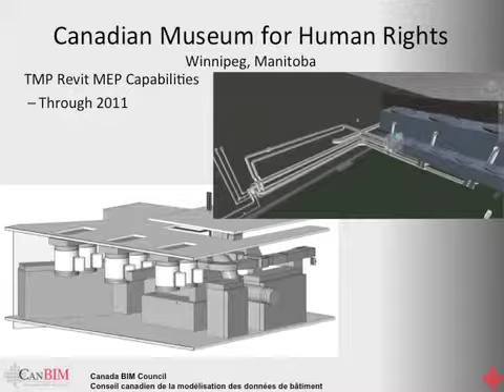This corner shot at the bottom shows 6 smoke exhaust fans, which we also explained to the city of Winnipeg, since high-rise building requirements call for 6 air changes of smoke exhaust for that space. I can't remember exactly, but I think it's close to 4 million CFM we have to exhaust out of it — it's phenomenal, just because of the volume of the space.